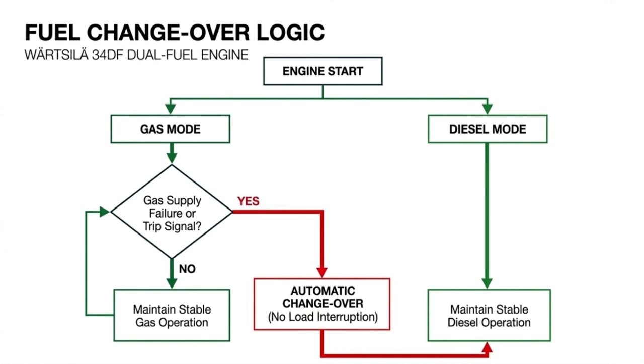Now, let us examine the control logic behind the dual-fuel operation. Under normal conditions, the engine operates in gas mode while the control system continuously monitors gas supply pressure. If a gas trip or pressure drop occurs, the system automatically transfers the engine to diesel mode. During this transition, the gas system is isolated and diesel injection immediately takes over combustion without interrupting generator output to the grid. This seamless changeover capability ensures stable and reliable power delivery during abnormal gas conditions. Next, let us see how LNG is conditioned before entering the engine fuel system.